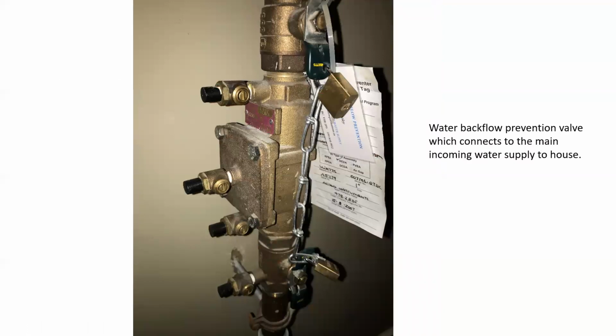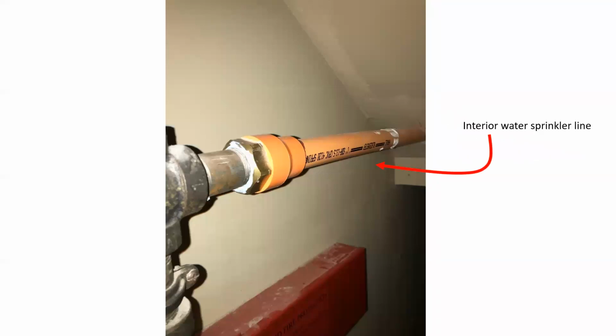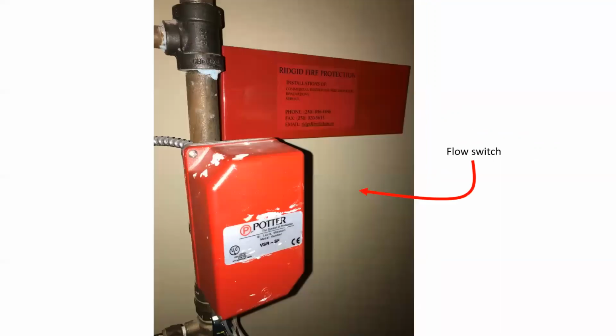There is a water backflow prevention valve, which simply prevents any water from getting pushed back into the main water supply and contaminating anything. It is then piped out through sprinkler system plastic piping, and this is colored orange to keep it very obvious and separated from any of the potable type water that would be utilized for any other portion of the house. These then go and connect to the different sprinkler heads throughout the residence.